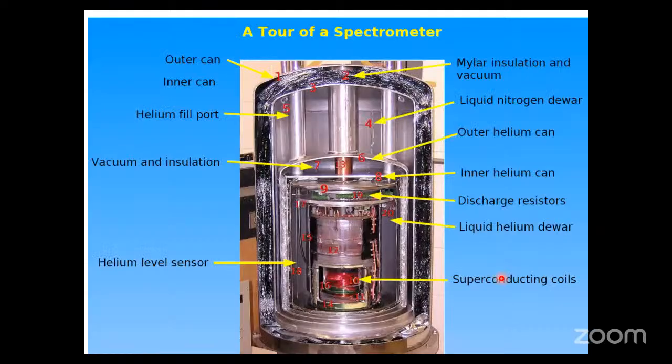This is the picture of the NMR machine. If you take the cross section, you will get this picture. So I'm talking about the superconducting coil, which is nothing but copper and some alloy they are mixing. Now this superconducting coil will have very, very little resistance at low temperature. And this low temperature, we can get by having the liquid helium over here.